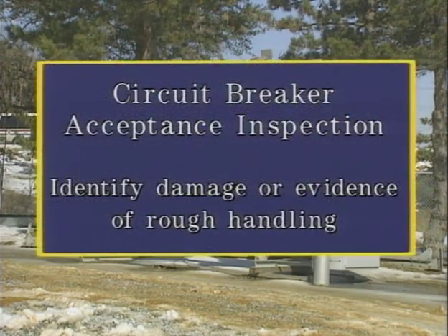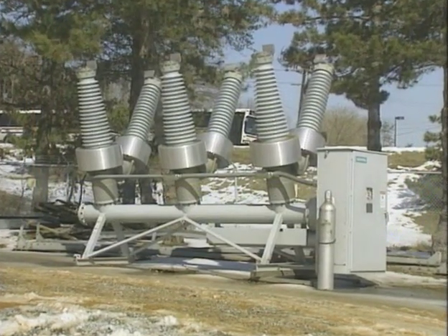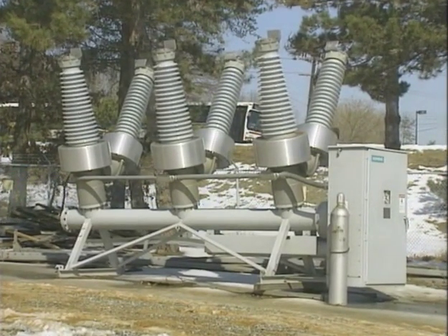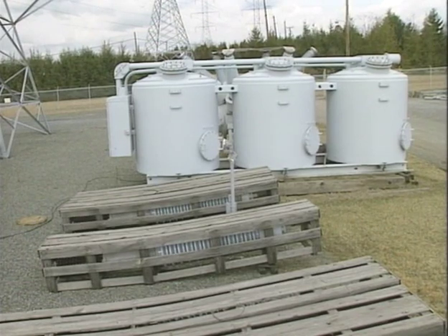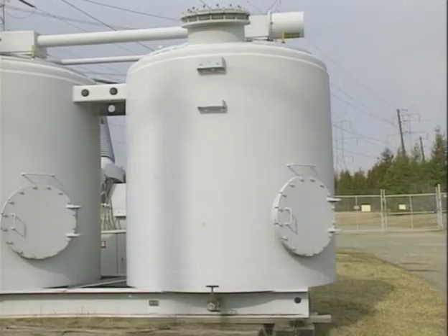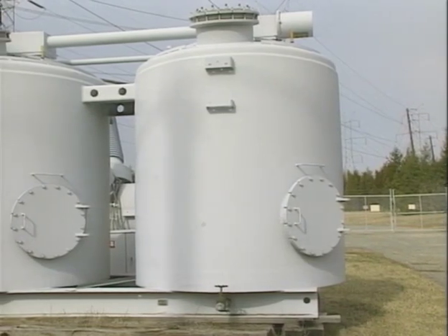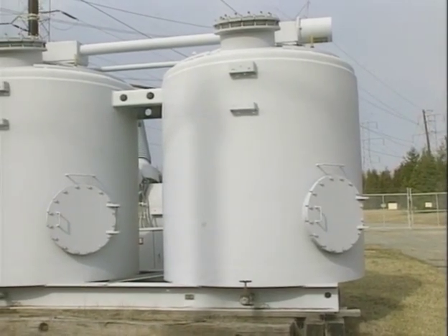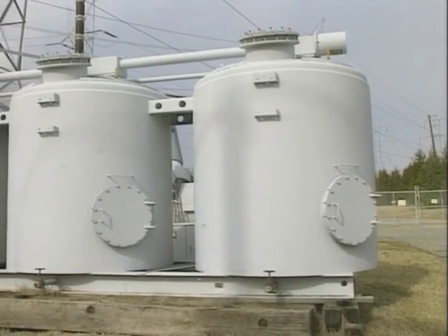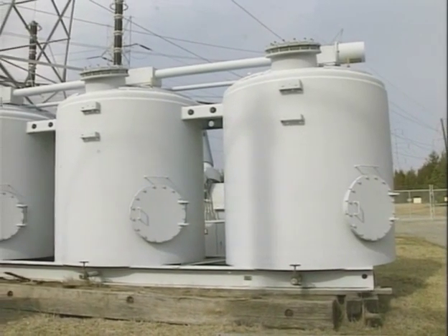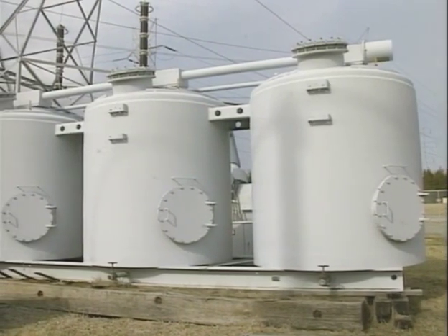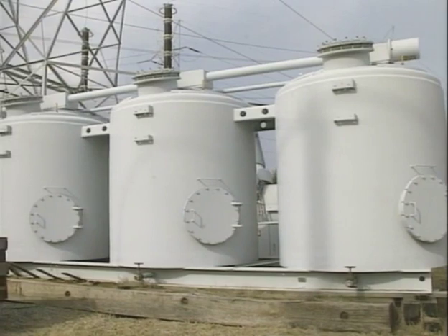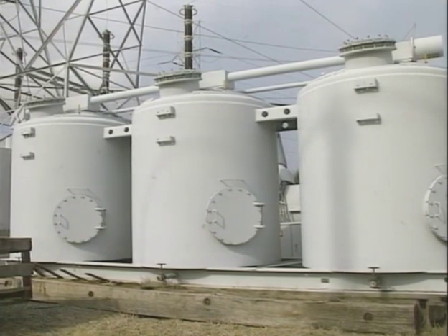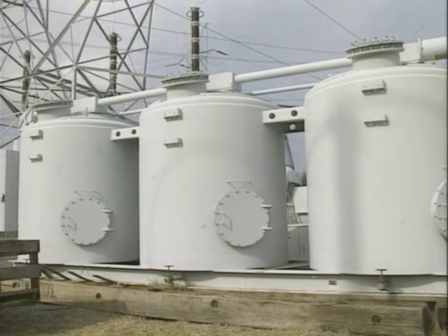The main purpose of an acceptance inspection is to identify any damage or evidence of rough handling before you accept the breaker. Many breakers, particularly smaller breakers, are shipped fully assembled. Others may be shipped with some of their components packed in separate crates. When the breaker is received, and typically before it's unloaded, the exterior of the breaker is checked thoroughly for damage or evidence of rough handling. For example, dents or creases in the breaker may result in leaks or structural weakness. Bent lifting ears or wings may have been caused by improper rigging that could result in internal damages.